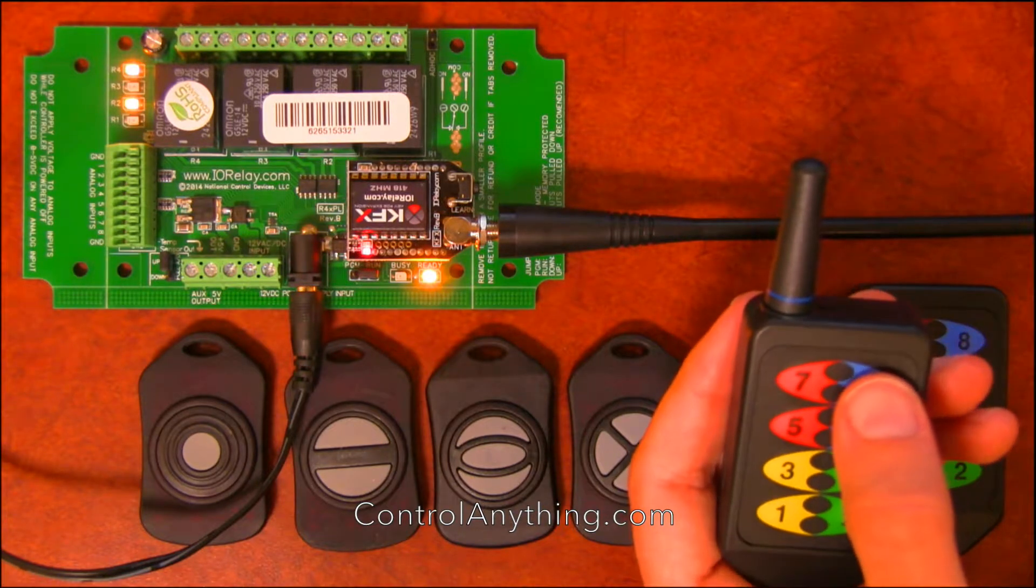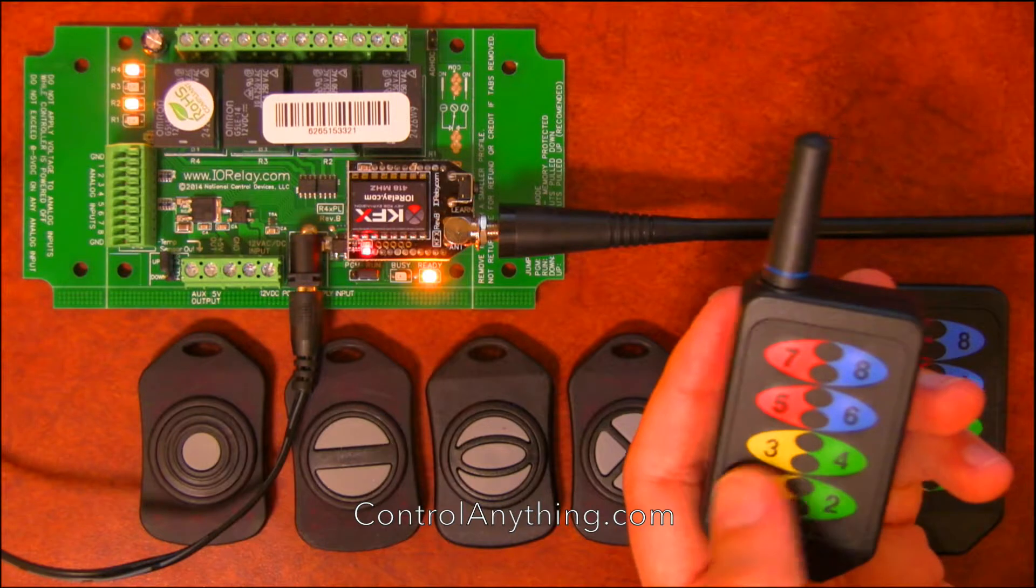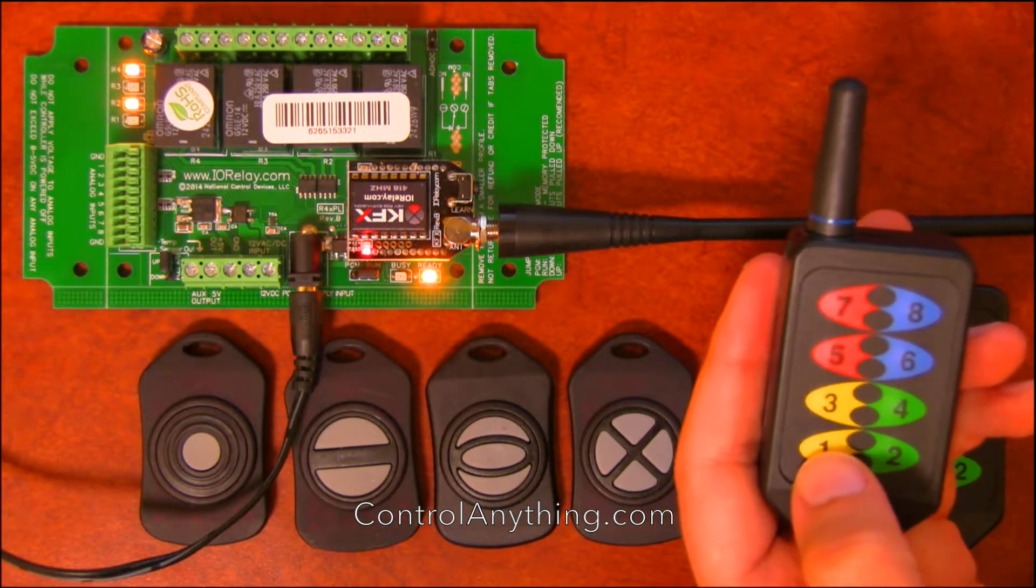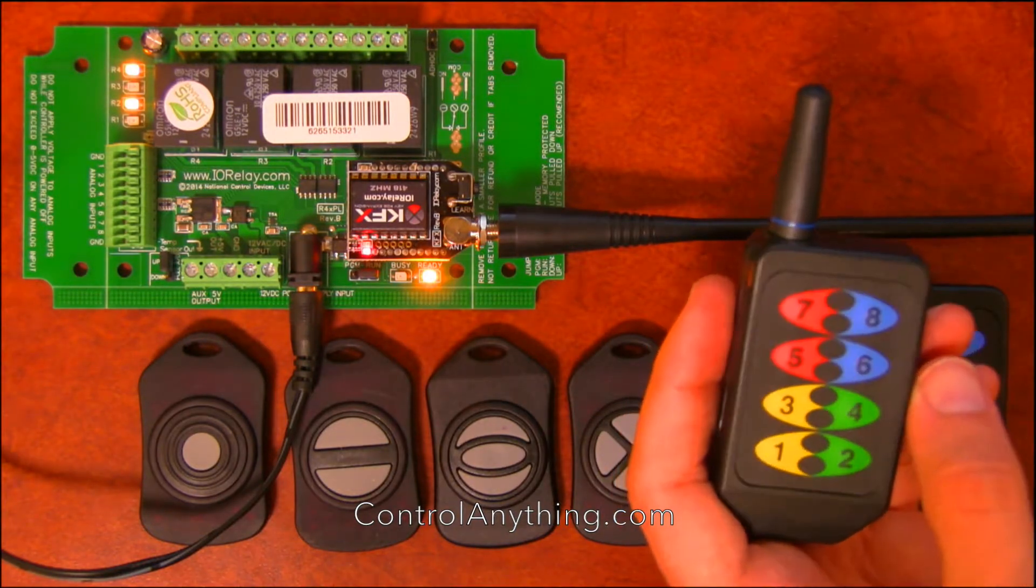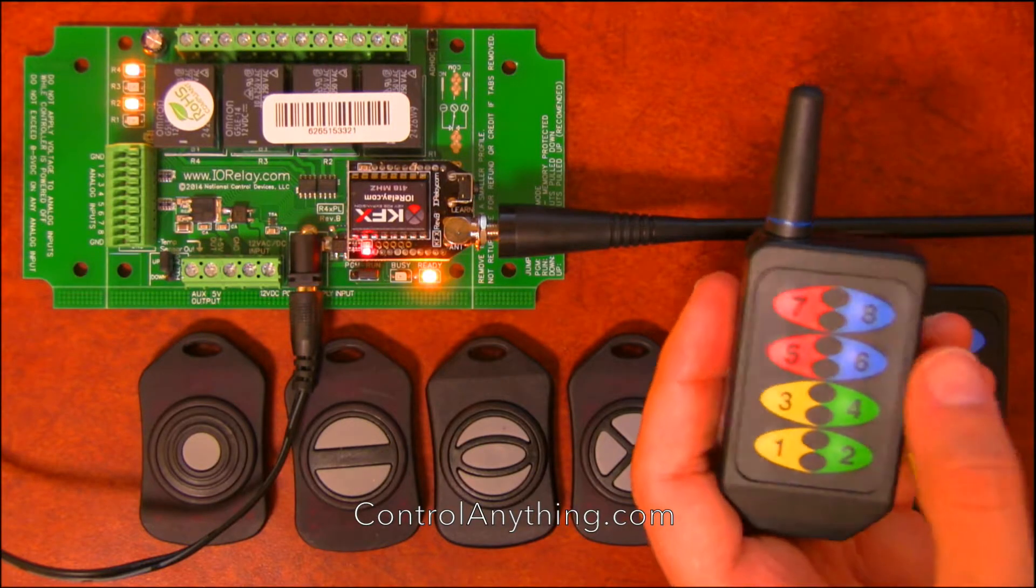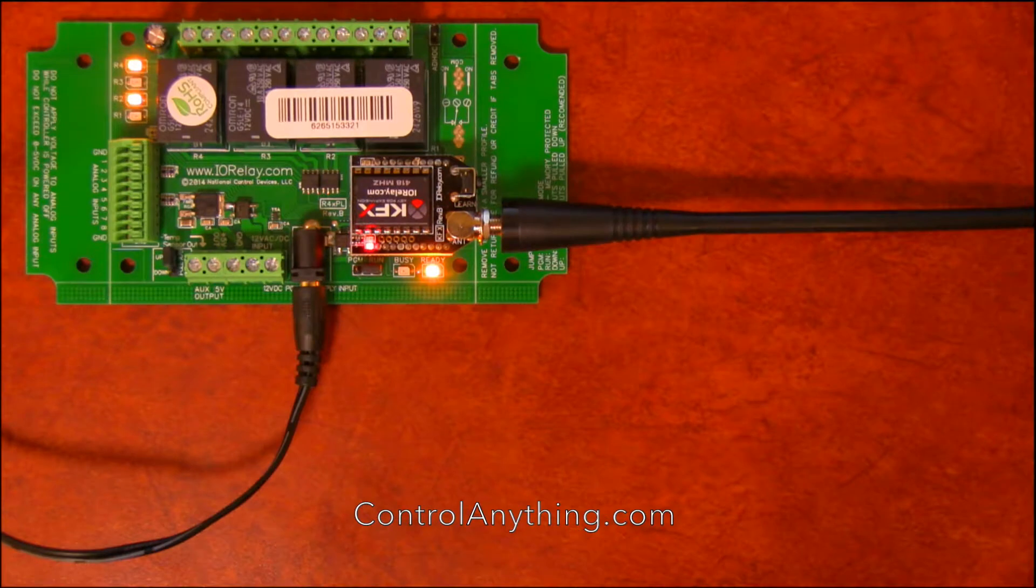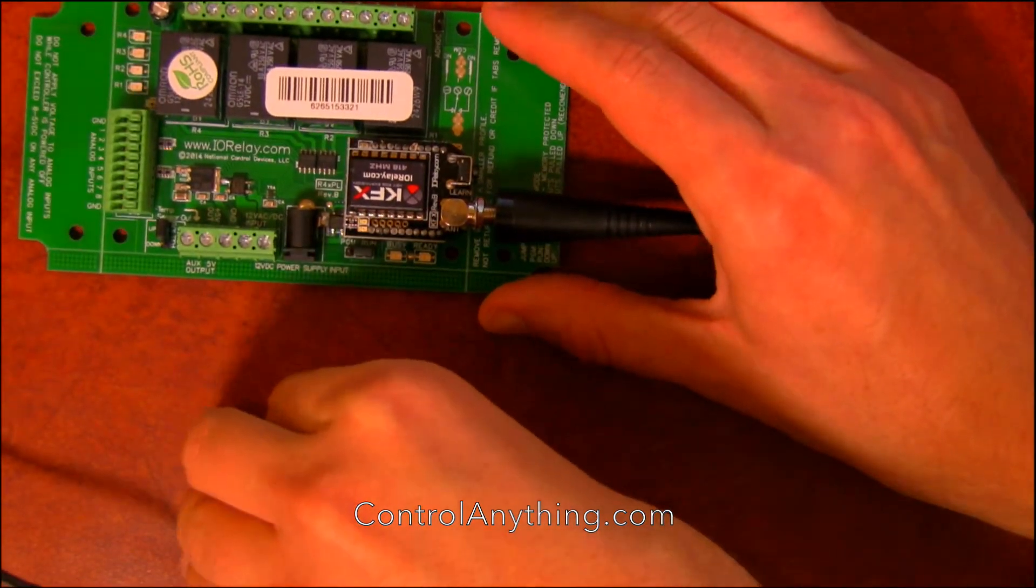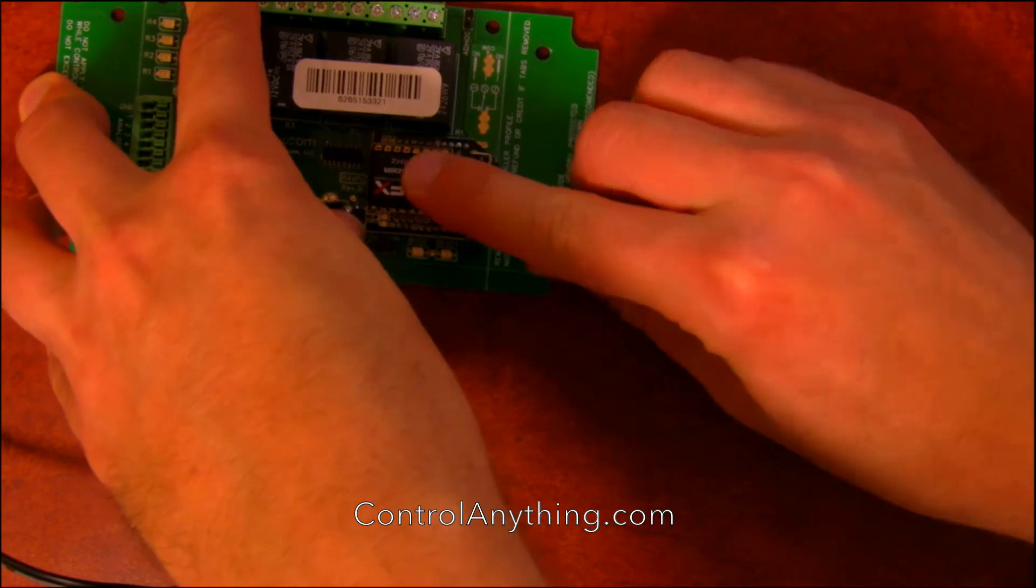So now let's take a look at how we configure a KFX module. We have a very in-depth article on this that we're going to be posting soon. But for now, we're just going to show you a really quick configuration of the KFX using the base station software. OK, to configure a KFX module, the first thing we want to do is disconnect power from the relay board and pull the KFX module out of the controller. This will allow us to put the KFX module into a configuration adapter.